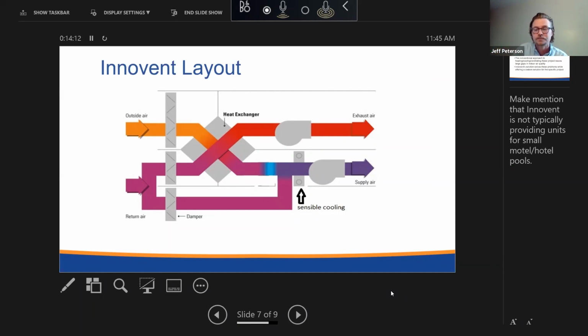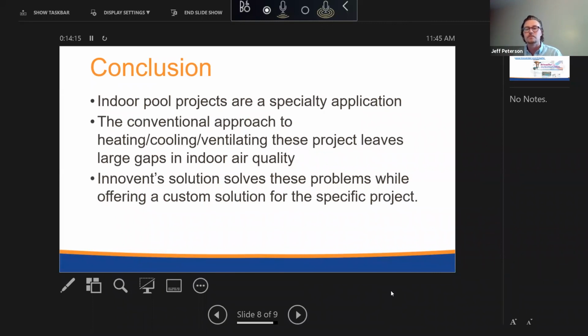So in conclusion, there's some specific things that you want to keep in mind, mostly indoor air quality, the risk associated with chloramines. The conventional approach to doing these types of systems, while it handles the space control, the temperature and the humidity, it kind of leaves the issues associated with chloramine buildup up to the owner. And if a problem occurs, it really doesn't leave you with any good options to alleviate that problem. Innovent's approach solves both of those problems. Not only is it an efficient solution, but it's utilizing that favorable condition of the outside air to do the dehumidification and to increase the amount of outside air that's in the space so that your indoor air quality stays in a good range.